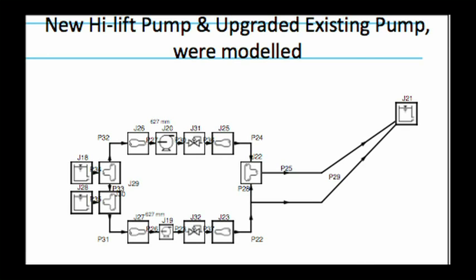But now, in all of these situations, this project's a little bit more interesting than just purely energy efficiency, because now you're juggling load shifting and energy efficiency, and what you have to do here to enable load shifting is often also an energy efficiency opportunity. And it was actually quite complicated getting funding out of Eskom, because differentiating what's load shifting and what's energy efficiency is quite tricky. We sort of predicted in future, if we were to upgrade the one high lift pump and install a new one in parallel to it, we could maybe get that down to 1 megawatt pumping power.